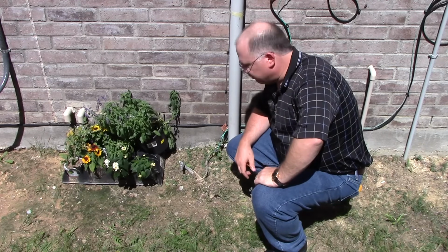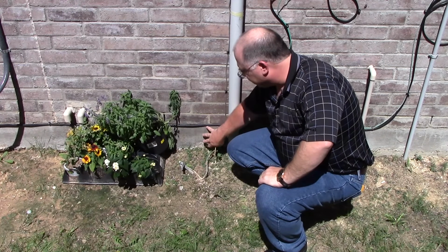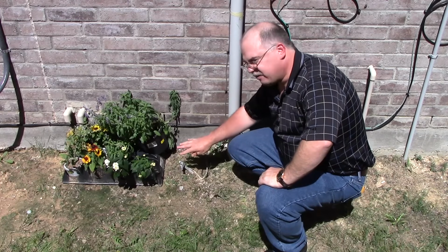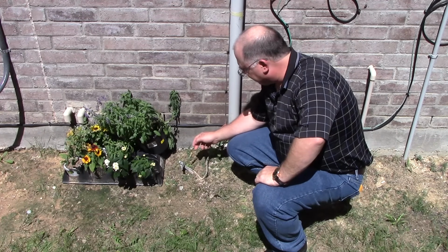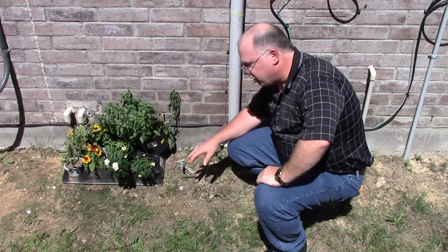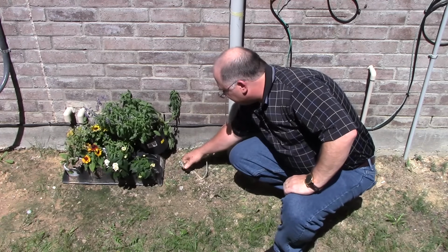I don't have any problem with this. I might recommend that this gets buried and tucked back, but it's not a requirement. We do want to protect this against physical damage. In this case, since this is exposed, it could be damaged, and in fact, this one I know is loose.